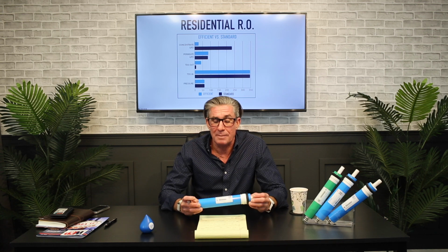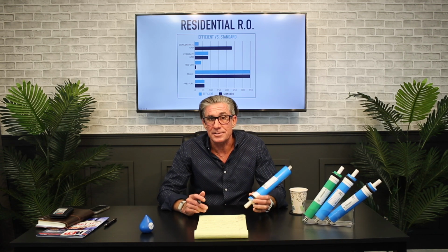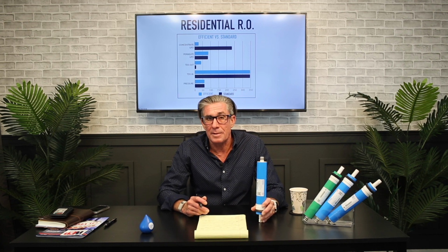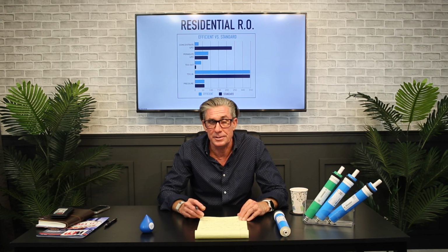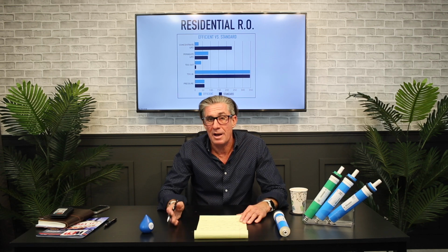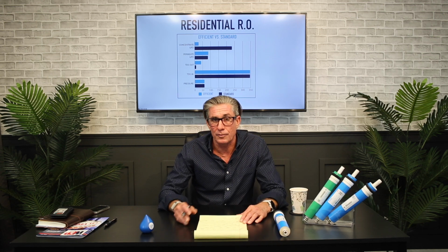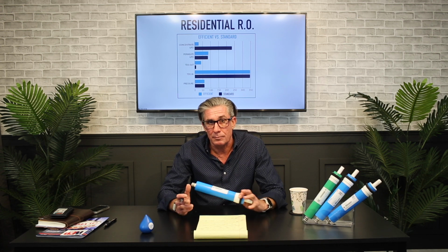Well, the way I properly test, and I suggest people test for membrane life testing, is if I start off by making, let's call it a gallon an hour for easy talking, and over the life of that membrane, if I get to 50% of my initial flow rate, so half a gallon an hour, over a 6-month period, I've basically fouled my membrane prematurely.